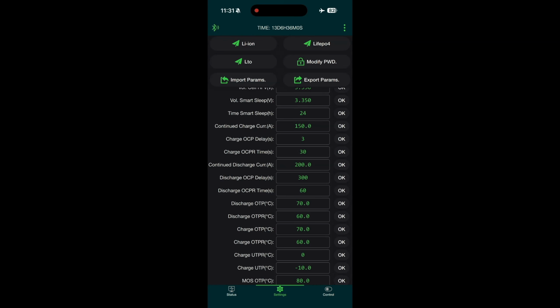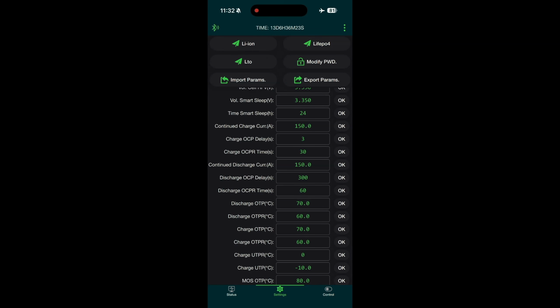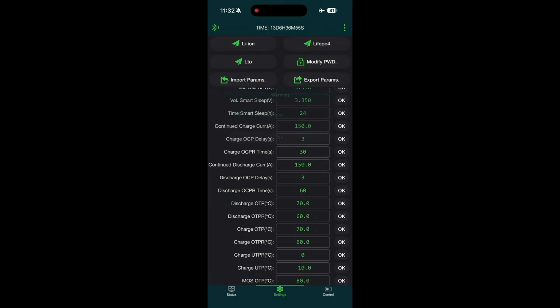Okay, continued discharge current. Again, this is a 200 amp BMS. If you're using a 5 kilowatt 48 volt charger, it's 104 amps going as a discharge. This is the same thing here. This is the maximum discharge current that you want to allow out of the BMS. So Discharge OCP is the Discharge Over Current Protect. Same thing as with the Charge OCP. What is the maximum amount of time, in seconds, before the BMS will disconnect? And again, I'll put this to 3 seconds.